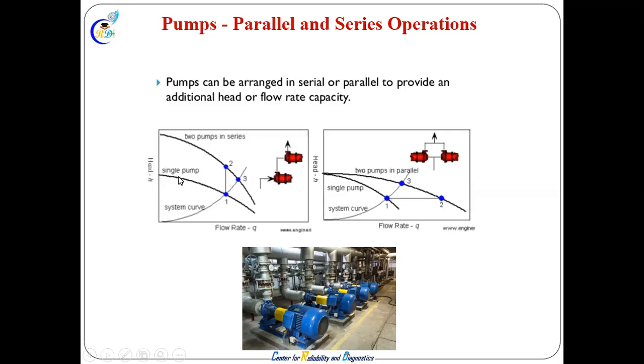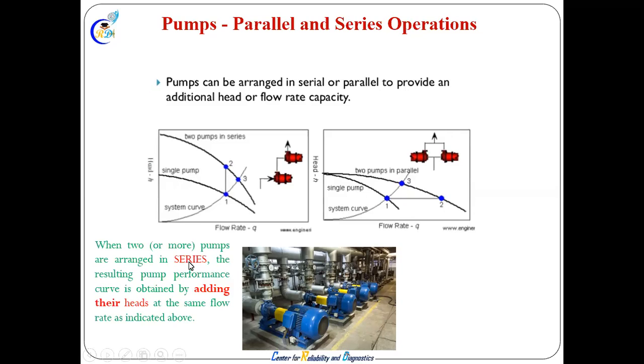In series it is different. In series, what happens? You are adding their head. So when you pump water from some dam here in Mumbai and get it to Panvel, and from Panvel another pump in series, again we want to keep the pressure head intact. So with more pressure head, you can do any number of series connections. In that, we are thinking about head increase, not the flow. So the flow will be the same, but we are increasing the head.